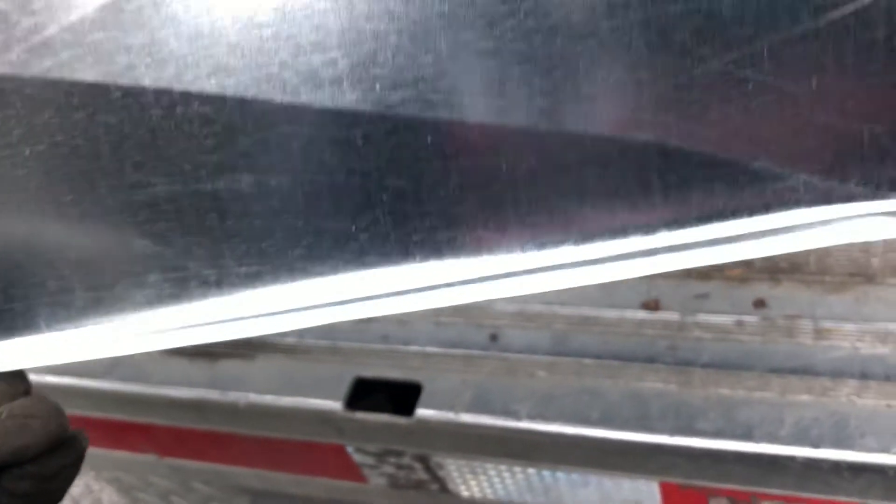Fold it over — you can see it there, bit of a glare here. Half-inch fold for the furnace, do a three-eighths fold to the S cleat, drive it in, and done. That's all there is to it. Thank you.